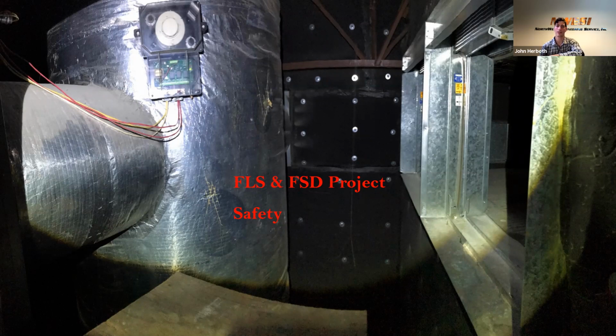The story I tend to use the most is I went to an assisted living facility that had 3 separate buildings, and 1 was newer and 2 were older, and they recently did a fire alarm panel upgrade. And we ran into the situation where I was testing the first building, everything was working great because it was a newer building. Yeah, some access wasn't great, some dampers were working, and then the other 2 buildings, nothing closed. So you had a building with 400 to 500 occupants that really need help getting out of the building, and no loss of life because no event happened, but they definitely had to go on fire watch immediately.